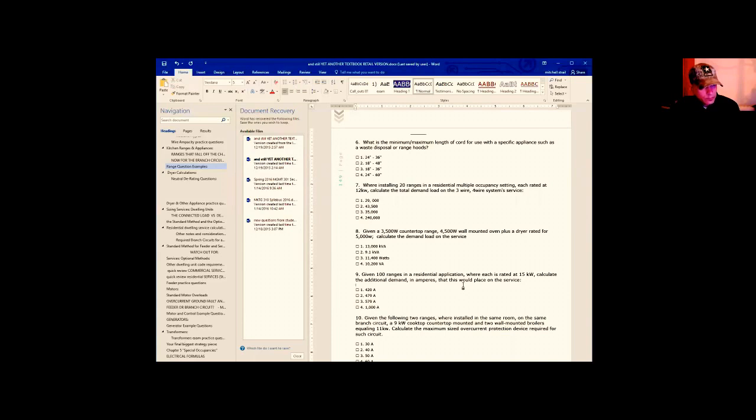How do you find the dryer? Is it the same thing? The dryer falls under 220.54, which is one page back from where you're at right now on page 71. And the first thing you got to know about dryers is actually under the article, which is listed on page 70. At the very last thing on the bottom right-hand column of page 70, it tells you they got to have at least 5,000 watts or a nameplate, whichever is greater.